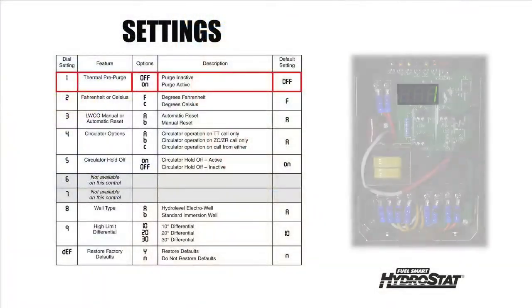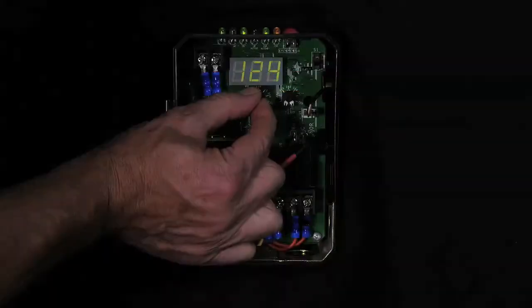The feature includes an internal algorithm that monitors the rate of temperature decrease. If it determines that the latent heat will be unable to satisfy the heat call, or if the boiler water temperature drops below 150 degrees Fahrenheit, the burner will fire immediately. This feature is turned off by default. So let's go ahead and activate this feature.